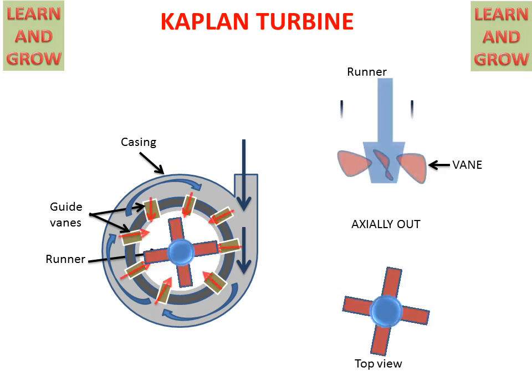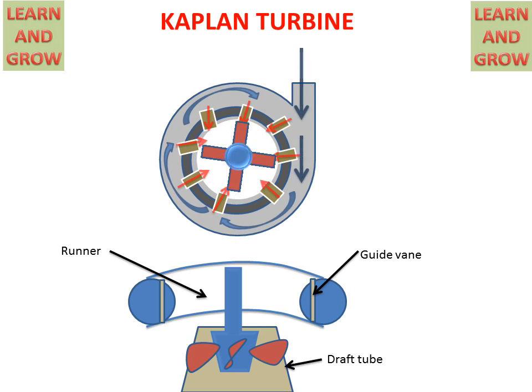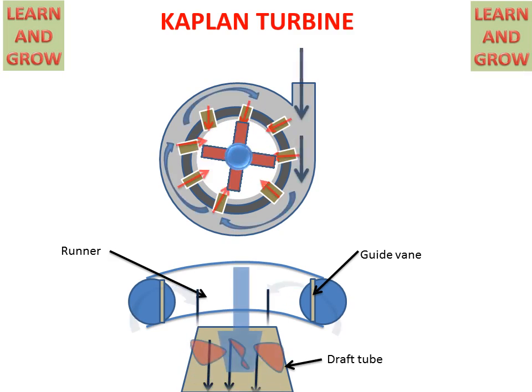Now we see the next figure for a clearer understanding. We have two figures: in the upper figure, water comes, rotates, enters from the guide vanes, and the runner starts rotating. In the lower figure, when water comes from the guide vanes, it axially strikes on the blades or vanes of the runner, then goes outside in the axial direction through the draft tube, and the runner starts rotating.